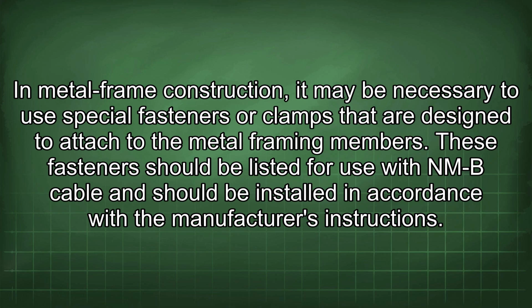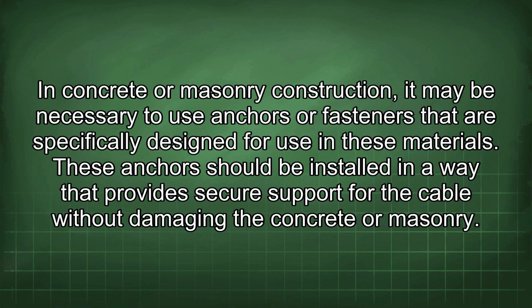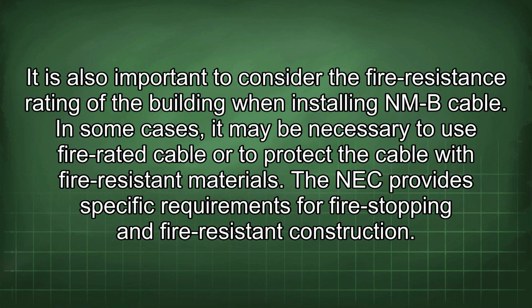with the manufacturer's instructions. In concrete or masonry construction, it may be necessary to use anchors or fasteners that are specifically designed for use in these materials. These anchors should be installed in a way that provides secure support for the cable without damaging the concrete or masonry. It is also important to consider the fire resistance rating of the building when installing NMB cable. In some cases, it may be necessary to use fire-rated cable or to protect the cable with fire-resistant materials. The NEC provides specific requirements for fire-stopping and fire-resistant construction.